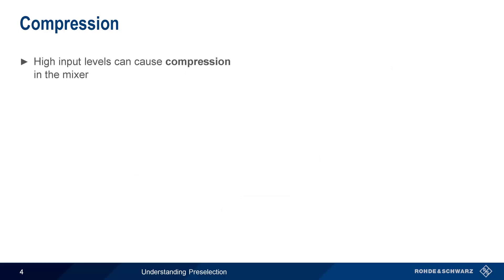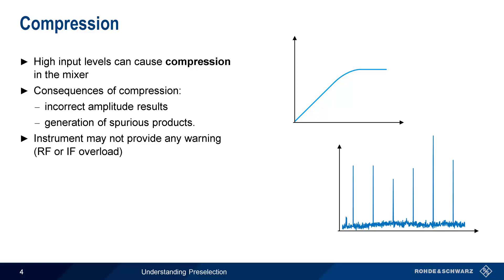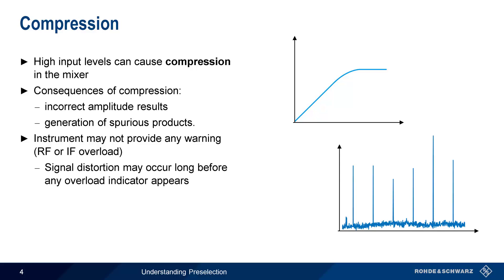Like all active devices, mixers are subject to compression at high input levels. Compression has several consequences, the most important being incorrect amplitude results and the generation of spurious products. Mixer compression is even more problematic because in many cases, the mixer may be in compression without any warning from the instrument, such as an IF or RF overload indication. The lack of an overload warning does not mean that we have no spurious products due to mixer compression. Signal distortion can, and often does, occur long before overload is indicated. It's especially important to remember that the signals causing mixer compression may be outside of our current measurement range or span. A high-powered signal can cause mixer compression even if we don't see that signal on our instrument display.